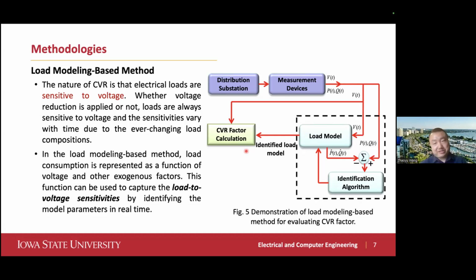You'll have a mix of constant power load, constant impedance load, and constant current load. This mixture changes with time depending on the load composition—depending on every one of us switching this device on or that device off. So overall, at the feeder head, the composition of constant power, constant impedance, and constant current parts changes with time because customers are switching their devices on and off.